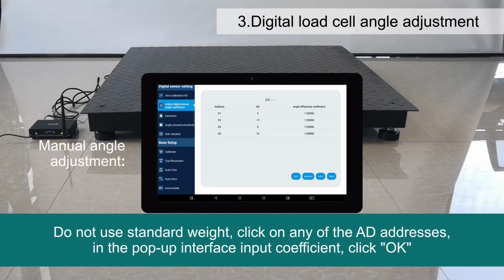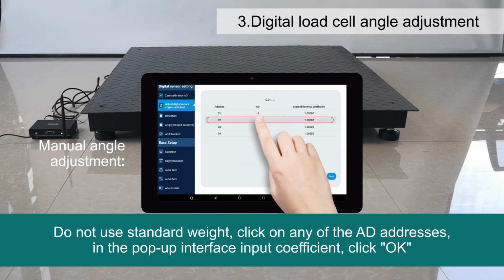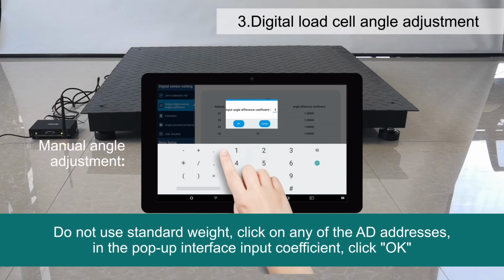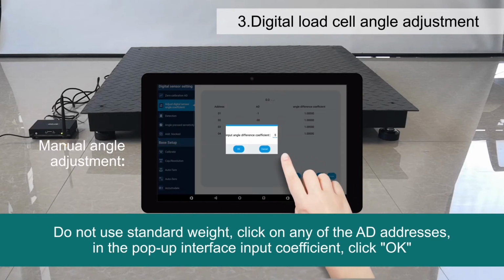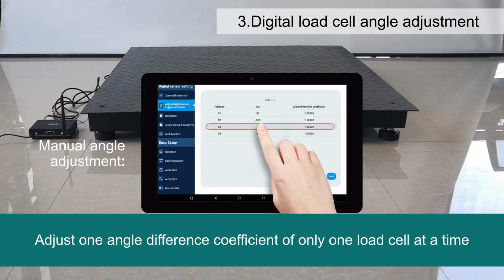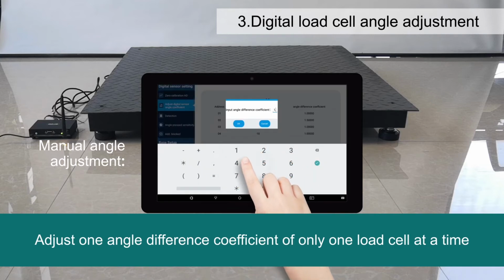Manual angle adjustment. Do not use standard weight. Click on any of the AD addresses. In the pop-up interface, input the coefficient and click OK. Adjust one angle difference coefficient of only one load cell at a time.